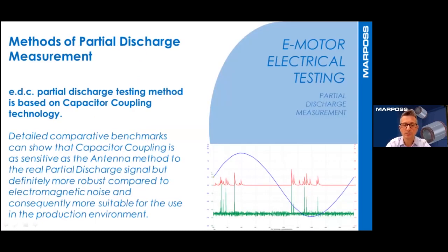EDC partial discharge testing method is based on capacitor coupling technology. Other solutions based on different technology are available on the market, such as the antenna method, which is the most popular, and it uses a special antenna to detect the electromagnetic radiation emitted by partial discharge. Detailed comparative benchmarks were performed by research institutes, such as Aachen University, to compare different measurement technologies, showing that the EDC capacitor coupling sensitivity is comparable to antenna, but it's definitely more robust compared to electromagnetic noise, so more suitable for use in the production environment.